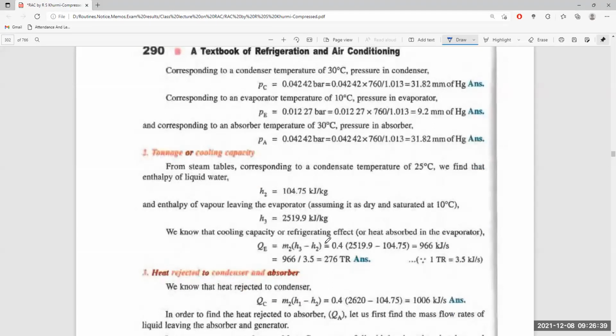Now, the cooling capacity or refrigerating effect, or heat absorbed, is the mass 0.4 multiplied by H3 minus H2, the enthalpy of the leaving refrigerant minus the enthalpy of the incoming refrigerant. That is equal to 2519.9 minus 104.75, which is equal to 966 kilojoule per second. One ton is 3.5 kilojoule per second, so if you convert it to tons by dividing by 3.5, that is 276 tons.